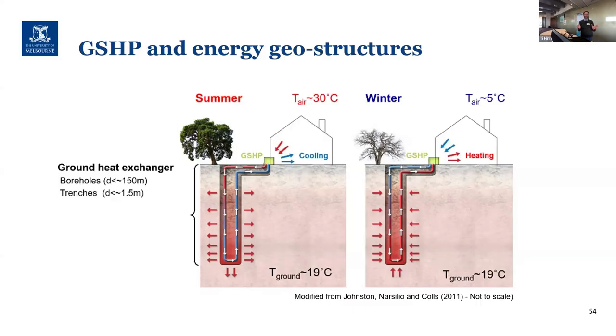This is not too different from a reversible split system at home. The big difference is that in summertime, your split system is rejecting heat to the air, which is already hot, so you need to use a lot of energy to move that thermal differential. And in winter, we do the opposite. We take heat from the ground, which is a much higher source of thermal energy than the air would be. A reversible air source heat pump takes thermal energy from the air, which in winter is much cooler than the ground. So inherently, the amount of energy or work that we need to put into the heat pump when we use ground heat exchangers is, on average throughout the year, typically lower than for an air source heat pump. And this is where the savings come from.